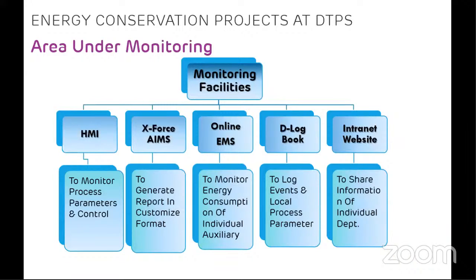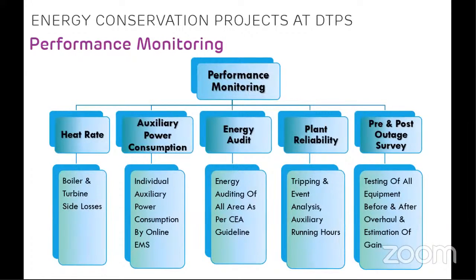And we also have an intranet website, which is our internal website where we share information of individual departments, and which is accessible to all employees of the plant as well as to visitors in case they want to see this information. Then for performance monitoring, like I said, we have heat rate, aux power, etc. In heat rate, we monitor boiler and turbine losses. Then in aux power consumption, we monitor the auxiliary power consumption of each auxiliary running in the plant by using the online EMS, energy management system. Then we conduct energy audit as per CEA guidelines.